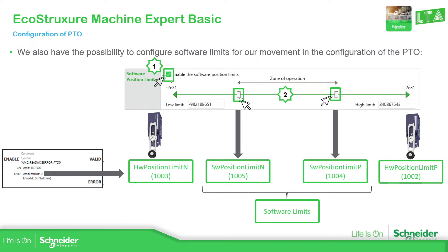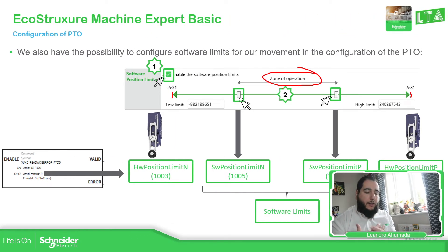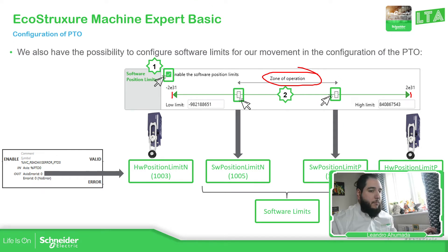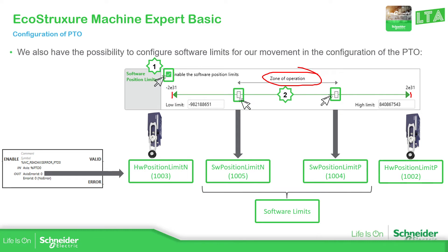The limits define the range that the axis can travel — this is the operation zone. Since we don't have direct feedback, the software counts the pulses being sent to the driver. By counting those pulses, the software can compare the actual position against the software limit switches to activate an error if the position reaches those configured values.